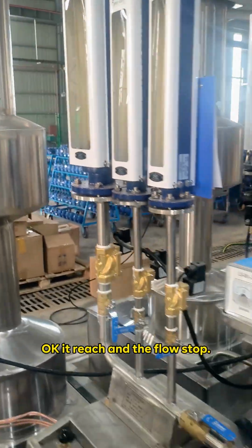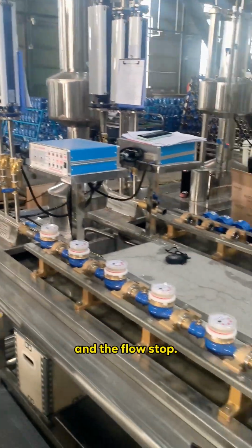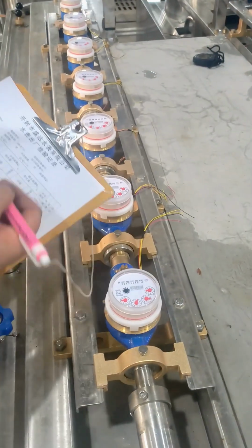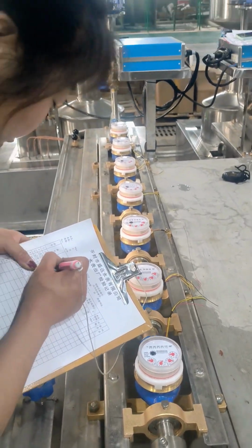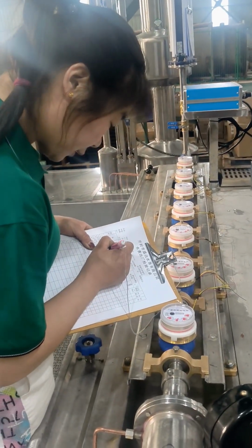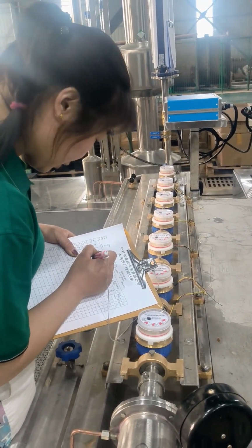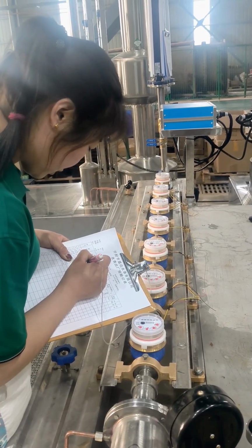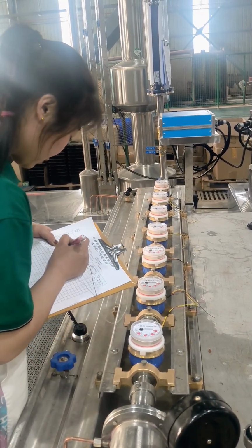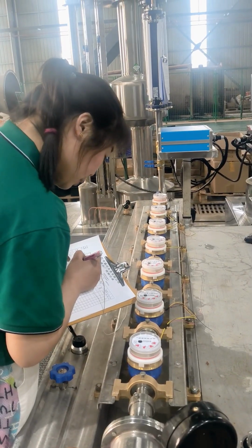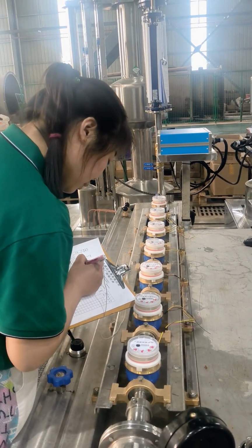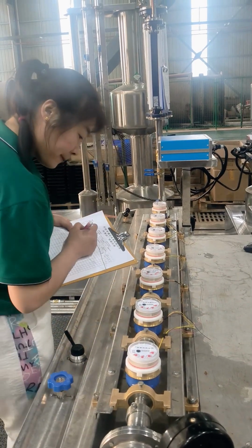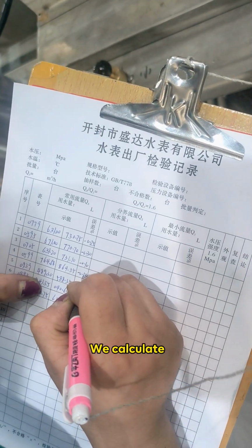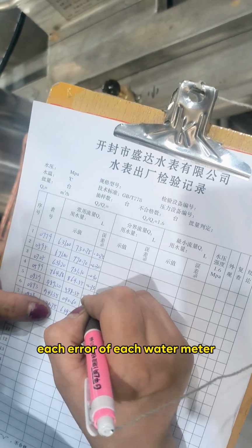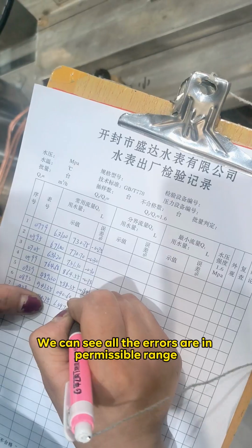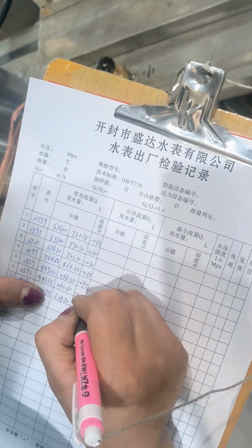Okay, it reached, and the machine is done now. Now we record the final data of the nominal flow, and we calculate the error for each water meter. You can see all the errors are within the permissible range.